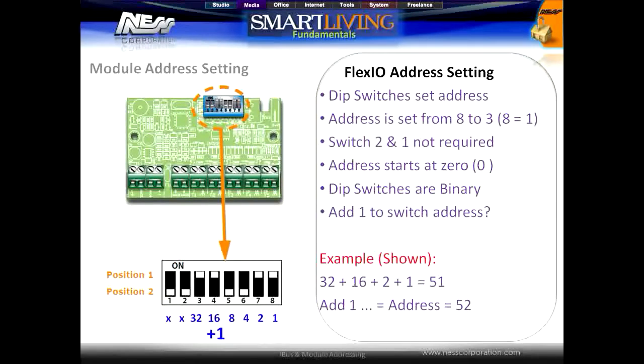In the example, switches 3, 4, 7 and 8 are switched on. This gives 32 plus 16 plus 2 plus 1, which equals 51. We then add 1 to the total to get the address of 52.